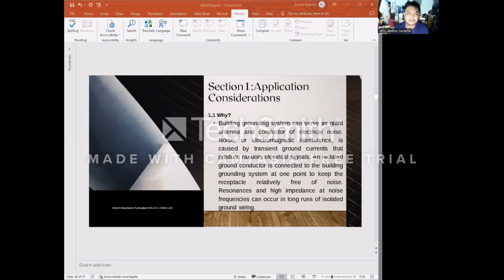Now, why should we consider this application? A building grounding system can serve as a giant antenna and conductor of electrical noise. Noise or electromagnetic interference is caused by transient ground currents that produce random electrical signals. An isolated ground conductor is connected to a building grounding system at one point to keep the receptacle relatively free of noise. Resonance and high impedance at noise frequencies can occur in long runs of isolated ground wiring.